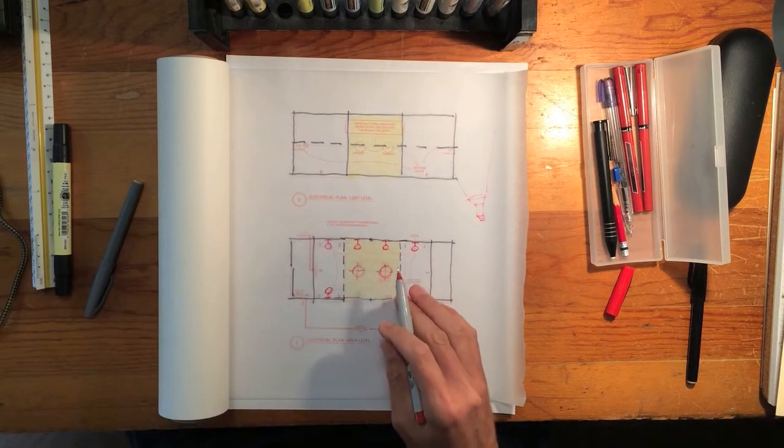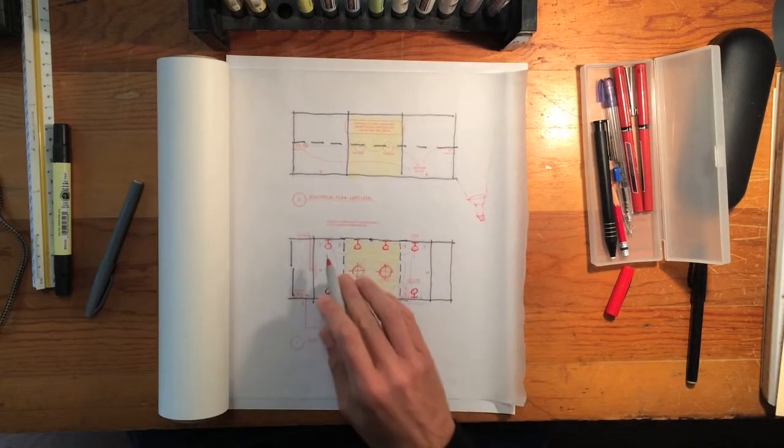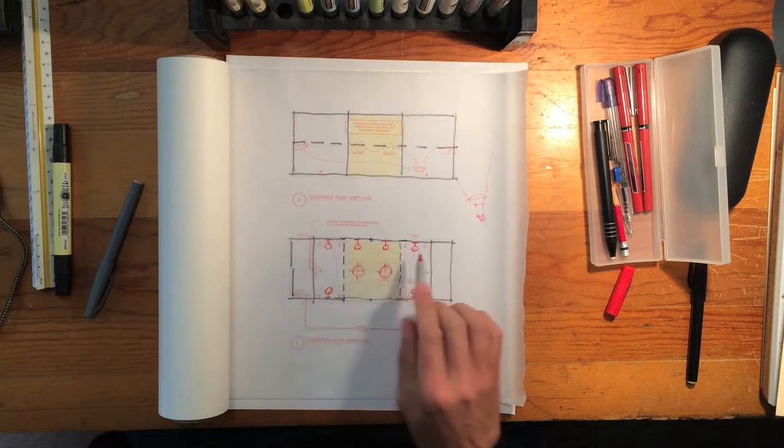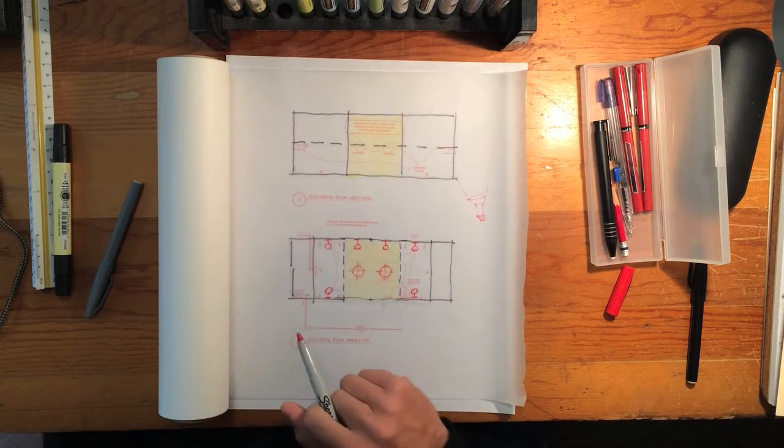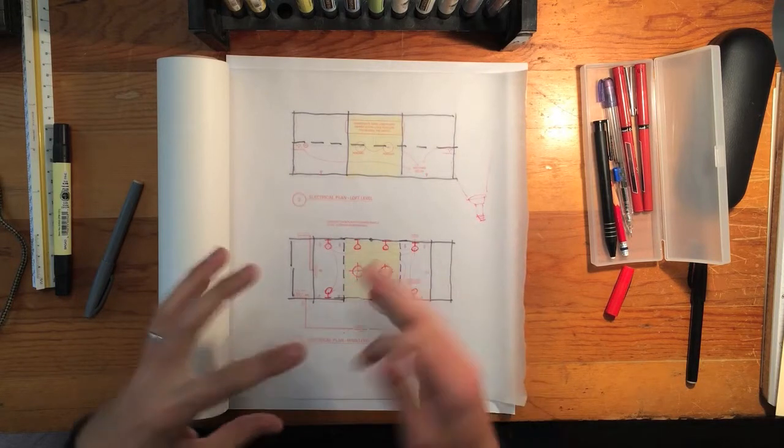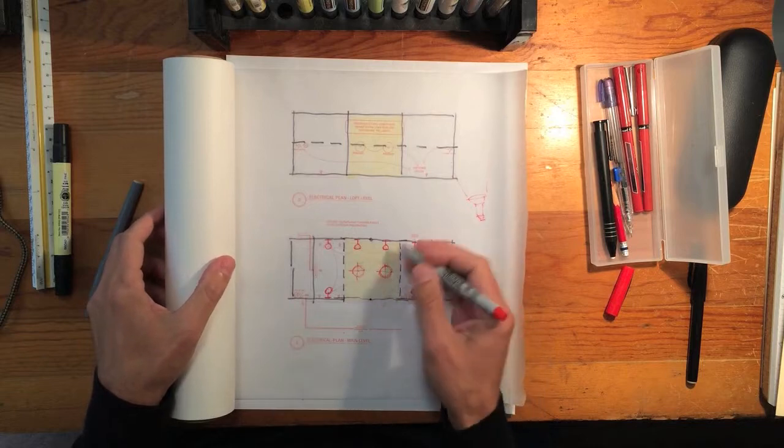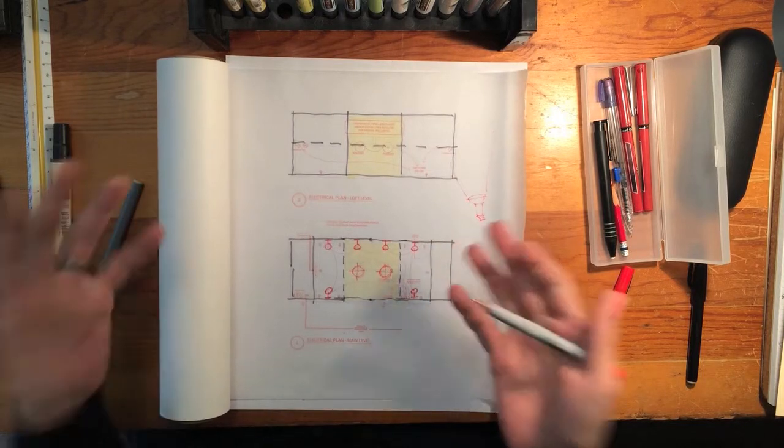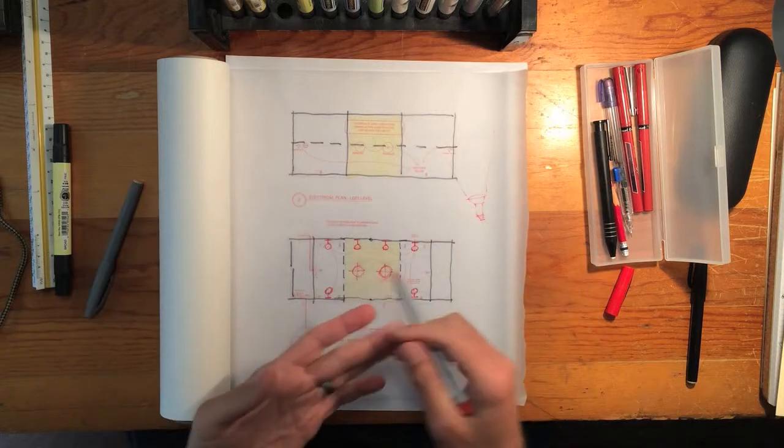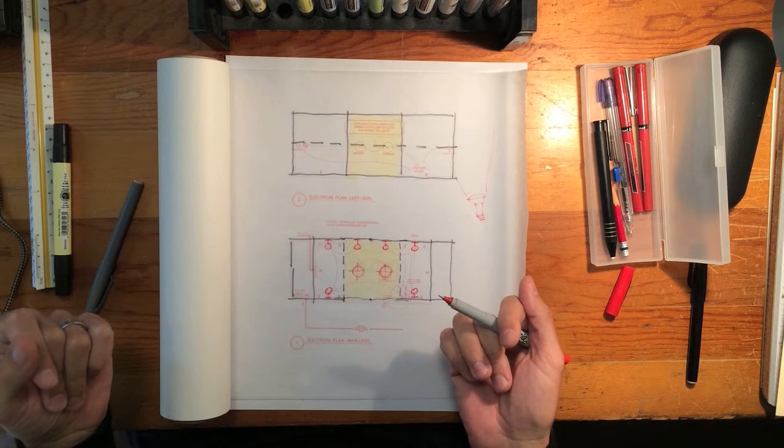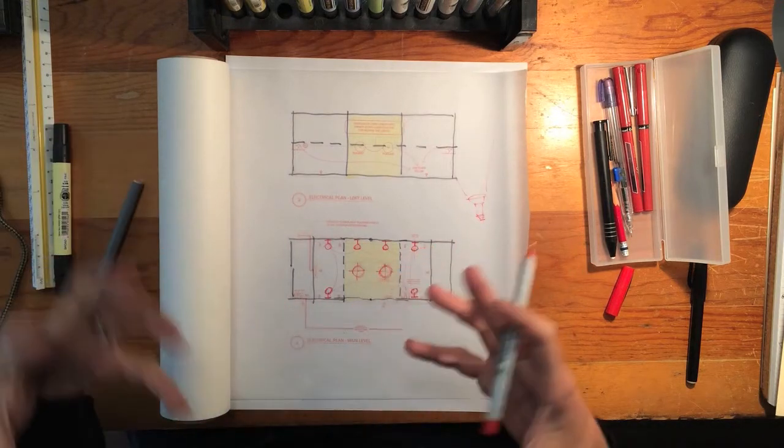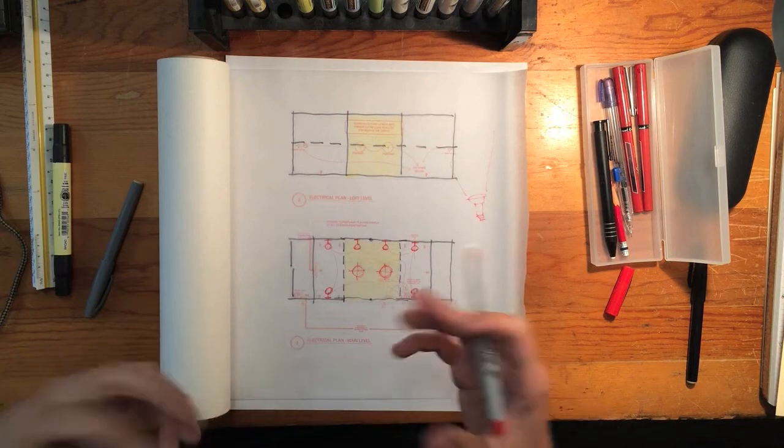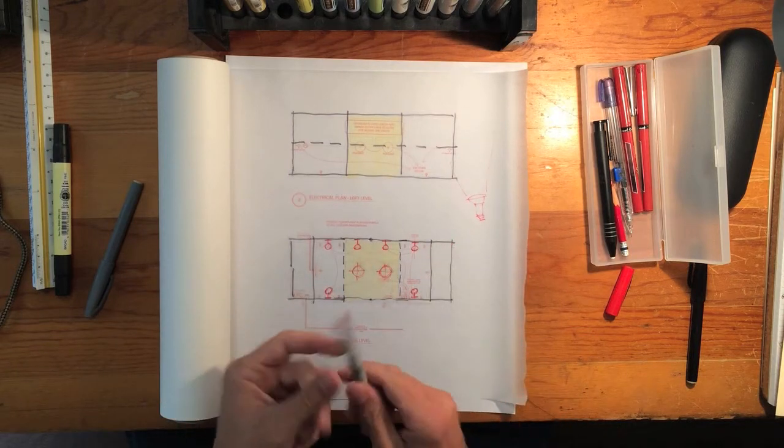So we've got our general illumination here. Now the lamps that this can hold for our ambient light can hold up to a hundred watts each, so if we total these up, that's about 600 watts of general illumination. We said our basic floor area calculation gave us a 450 figure. What I like to do is keep all of these fixtures on a dimmer switch, and that will allow you to set the ambient light level and set the mood however you want it to be. So it's okay to have a space over-lit as long as you have some way of dimming it down and controlling that.